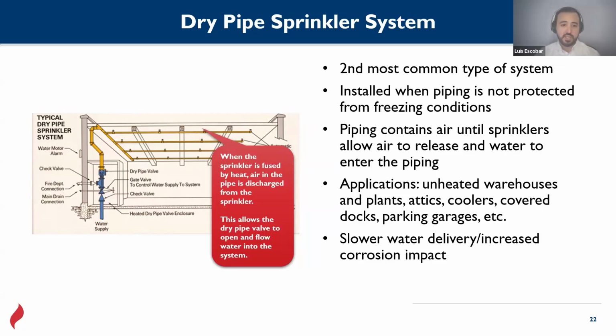Okay. Applications: unheated warehouses and plants, attics, coolers, covered docks, parking garages, etc. It could also be a good option for outdoor systems. For example, when there are freezing conditions, we can use these systems. The disadvantage of these systems is that they are more likely exposed to corrosion, and the maintenance is obviously costly. That's why these are common, but not as common as the wet systems.